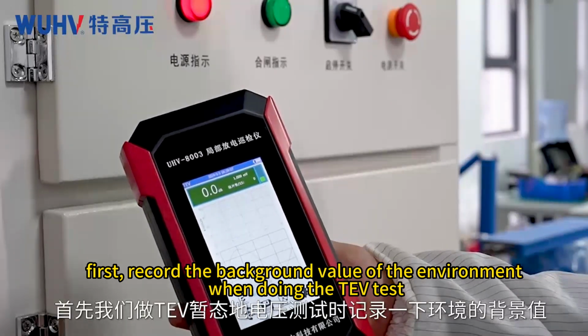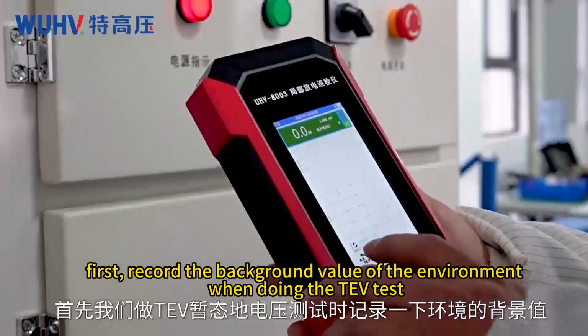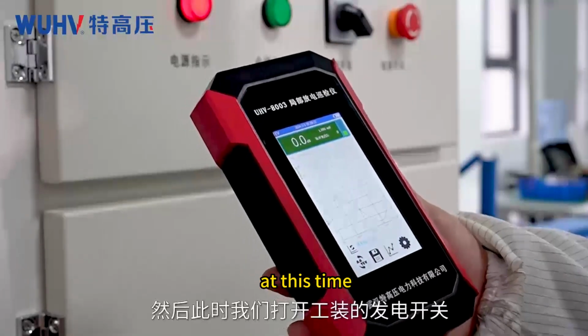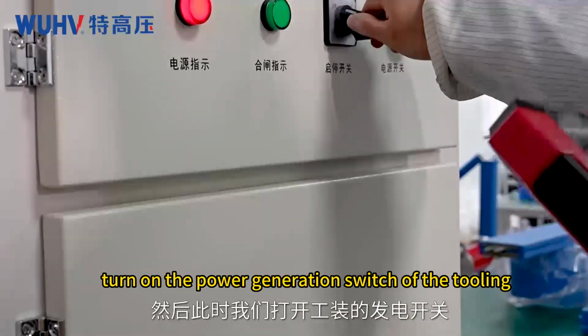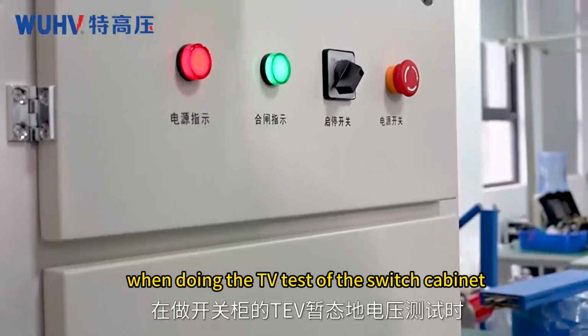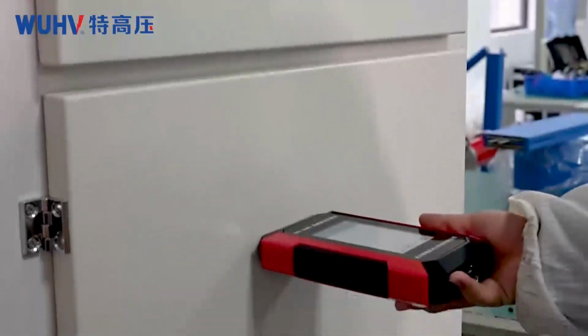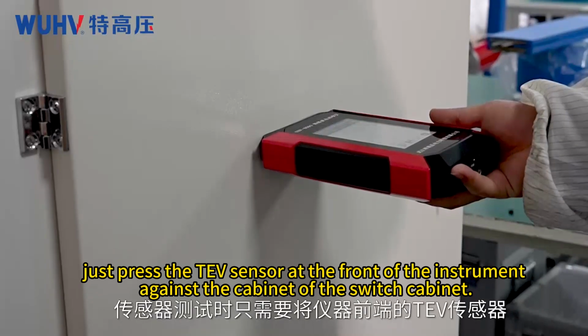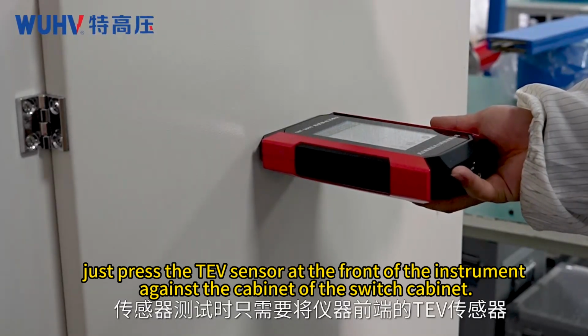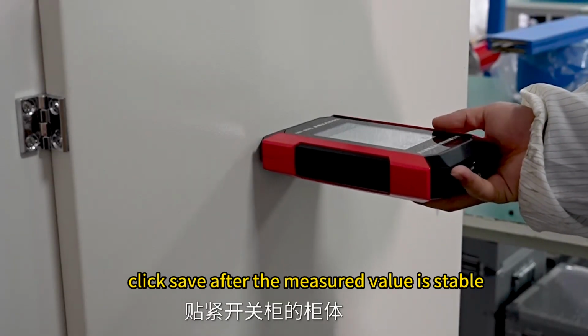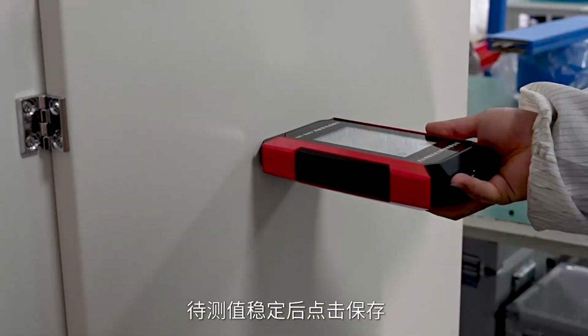First, record the background value of the environment when doing the TEV test. At this time, turn on the power generation switch of the tooling. When doing the TEV test of the switch cabinet, just press the TEV sensor at the front of the instrument against the cabinet of the switch cabinet. Click Save after the measured value is stable.